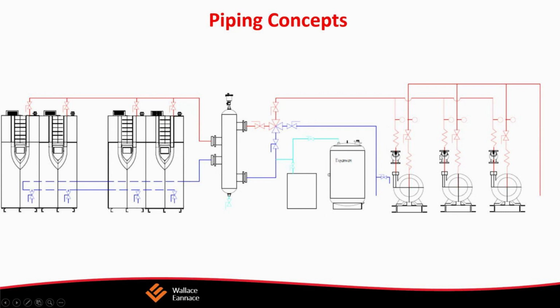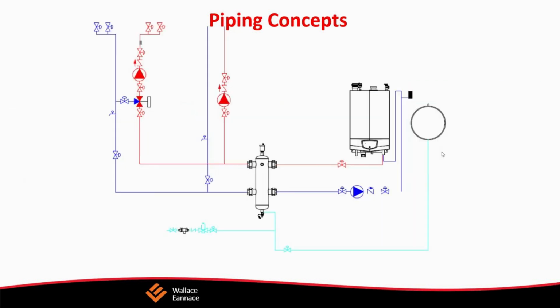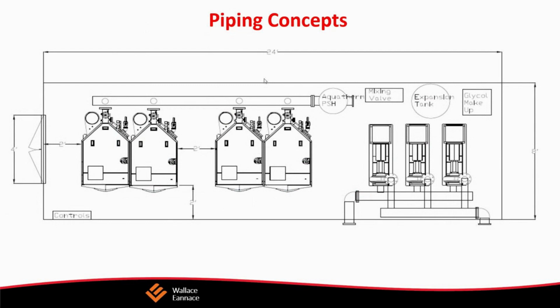Why would you do this? Why not use a primary secondary header? Well, if you look, you could have some very small zones over here. This comes out and goes to a bunch of zone valves, so we could have really small zones in this radiant loop, so that you could have calls for heat for very small spaces. Typically, if you have a vestibule and entrance, and a lot of kids coming into the kitchen where you have a lot of traffic, that space could constantly call for heat, and it requires very little heat to heat that space up. What that could do is short cycle the boiler. And as a solution to that, we offer a buffer tank in lieu of a primary secondary header.